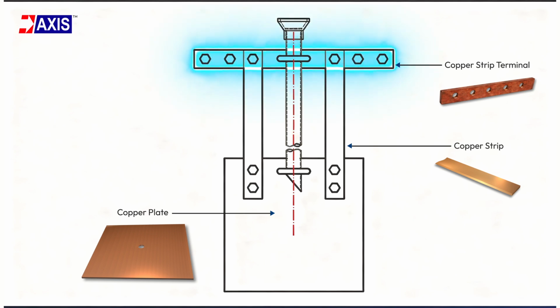Now thirdly, the copper strip terminal. This terminal is the flat bar mounted at the top of the pit where the copper strip ends. It gives you a clear and stable point to connect the strip to the earthing system above the ground. The terminal has multiple holes so that you can bolt the strip securely and make future inspection or maintenance easy. Its job is simple: to hold the strip in place, provide a firm mechanical support, and ensure a clean electrical connection between the buried earthing system and the equipment on the surface.